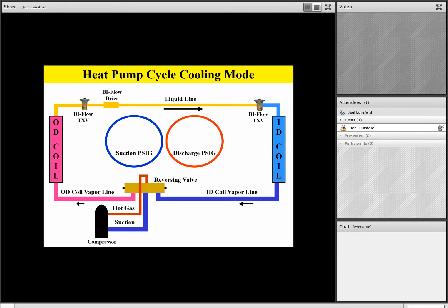In the cooling mode of operation, that hot gas from the compressor is diverted to the outdoor coil, which is acting like a condenser in the cooling mode. We then condense that hot gas from the compressor into a liquid. We pass that liquid through a biflow metering circuit, specifically a biflow TXV. Now remember, team, whenever we're talking about a TXV, the same component is also known as an expansion valve. So you'll hear that terminology interchangeably today. TXV and expansion valve are the same thing.